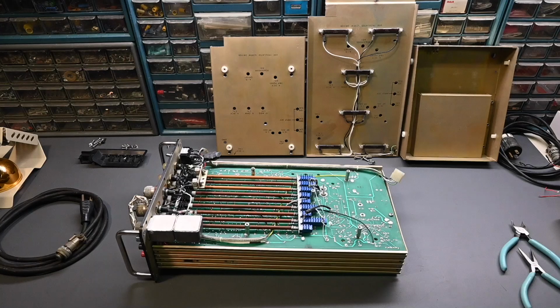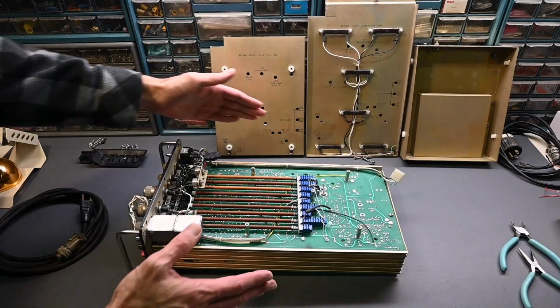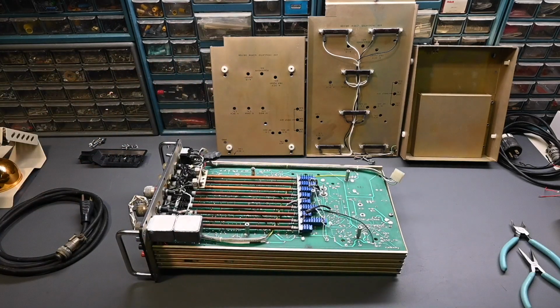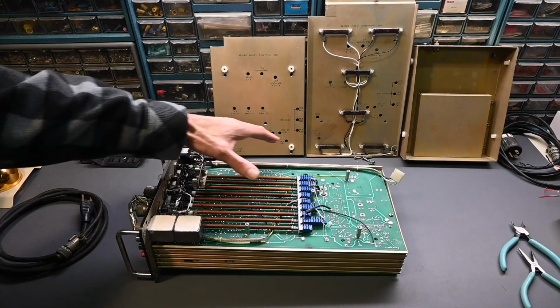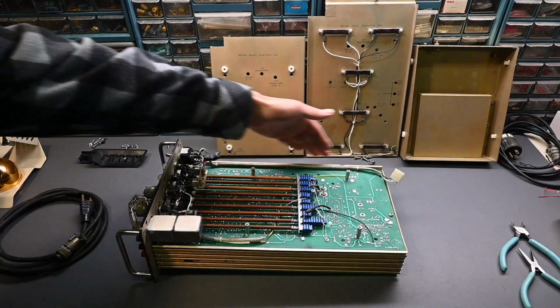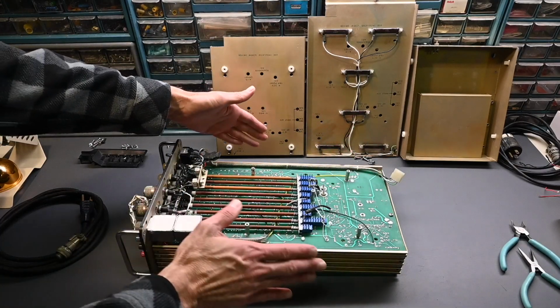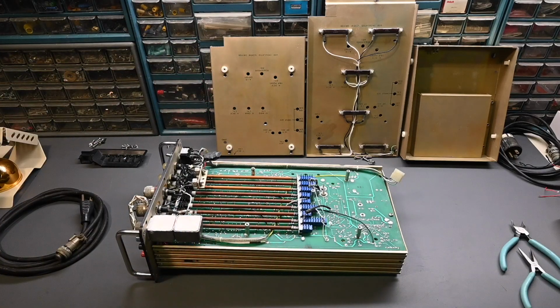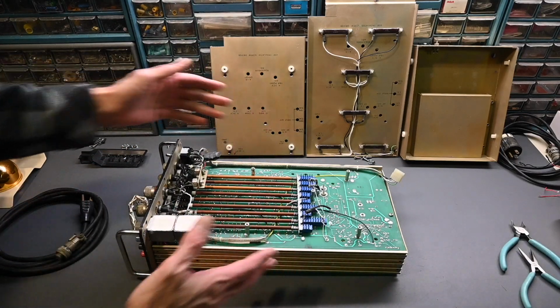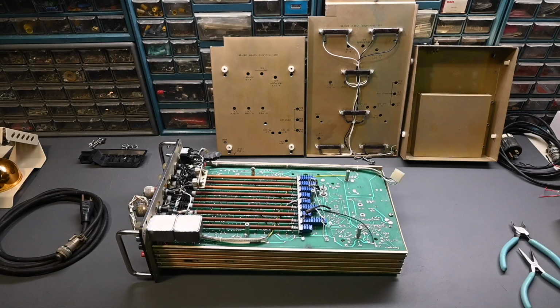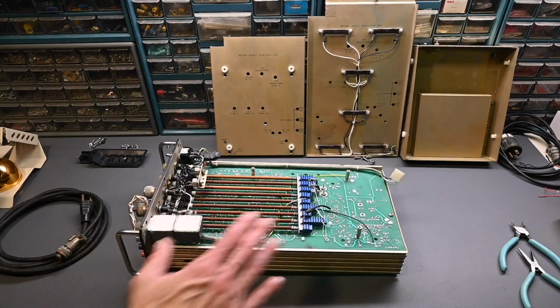It's really amazing given the physical condition of this multimeter—this whole frame was sort of twisted and tweaked out of position. I'm noticing some areas that will need attention once all the electrical work is done and the meter is actually working electrically. I'll want to spend time on the mechanical side fixing the frame; there are some areas that are bent, and I think the whole frame needs to be removed and straightened out. With something like this, you never want to hammer on the frame to straighten it—it needs to be pressed or squeezed. It'll take a little work, but it's certainly possible. I've been looking at how it comes apart and what needs to be done, so that will obviously be later on.